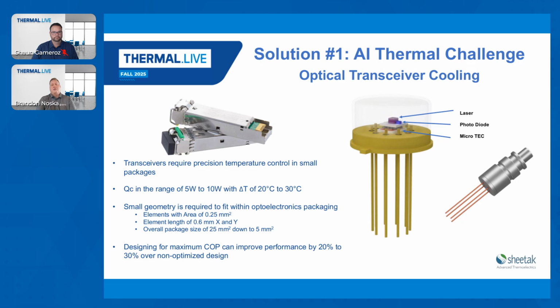Jumping into some actual applications related to data centers and AI thermal challenges that Sean was mentioning, one of the main areas thermoelectrics are being used today is optical transceiver cooling. This is an area where we continue to push the limits of traditional bulk devices, which require small form factors to fit into the packaging needed for these optical transceivers. Typically, on the right-hand side, you'll see a TO can with a thermoelectric device mounted to it, and the heat is dissipated through that. On the cold side, or temperature control side, is the laser diode, and sometimes a photodiode and other components that make up the system.